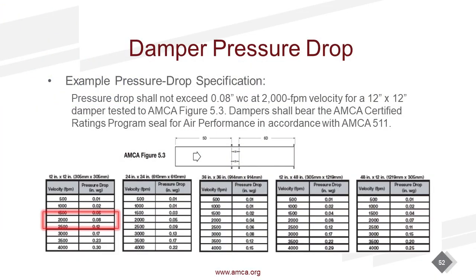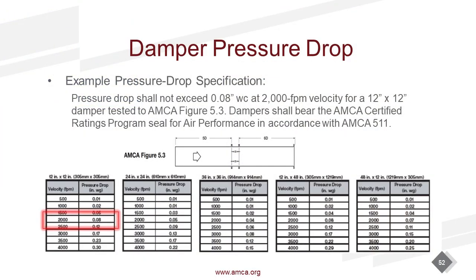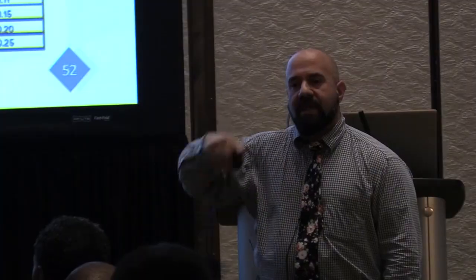This is a pretty typical pressure drop specification in the industry. We pick a single certified rating point, and we write that dampers at this rating point should not exceed this pressure drop. This is a certified rating for a 12 by 12. That is not a certified rating for a 12 by 13 or an 11 by 13. Only these 5 sizes are certified. This type of pressure drop specification does not guarantee anything other than that one damper's performance will meet that requirement. So if you have a sensitive application or you want to make sure you're designing efficiently, think about what pressure drop values you're using to estimate your system, and then maybe think about scheduling dampers.